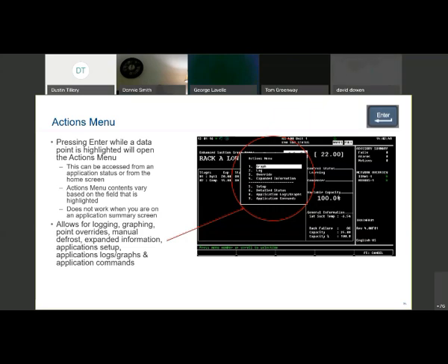You can also override that information here via that actions menu. Press number 3. Would be good for things like turning on compressors. If you wanted all of those compressors to come on at one time, you could go in and override that suction pressure above the set point and bring them all on. Again, it allows for the logging, graphing, point overrides, manual defrost, that type of stuff, all from one central location.